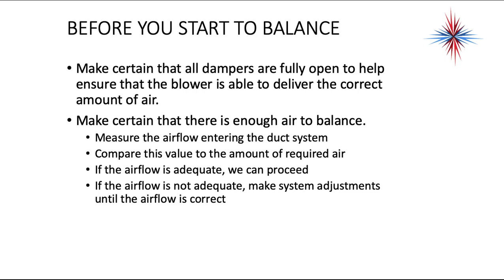Before you start to balance, there's a procedure to this whole thing. Make certain that all the dampers are fully open to help ensure that the blower is able to deliver the correct amount of air — always start with all dampers in the open position. Then you have to measure the airflow entering the duct system to make sure there's enough air to balance. If airflow is not adequate, you've got to make some system adjustments — might be increasing blower speed, verifying there are no leaks, or the system may not be sized correctly for the ductwork.